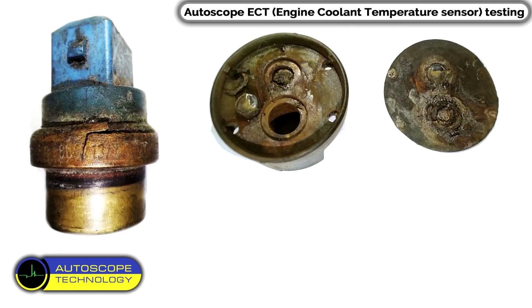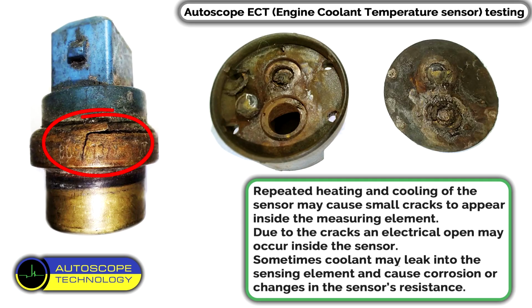Conclusion: repeated heating and cooling of the sensor may cause small cracks to appear inside the measuring element. Due to these cracks, an electrical open may occur inside the sensor. Sometimes coolant may leak onto the sensing element and cause corrosion or changes in the sensor's resistance.